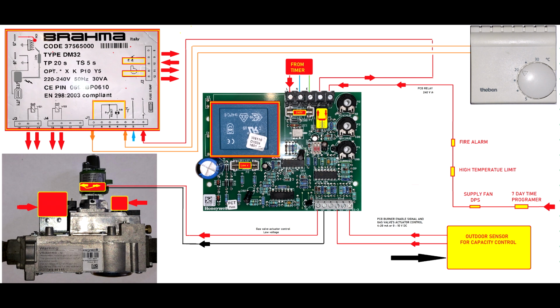And even if the Brahma controller is enabled and the control capacity is enabled, it doesn't mean the Brahma controller will initiate the heating, because you see you have a thermostat, and the thermostat is supposed to close the circuit between 3 and 7. And at the moment this system is on standby. Outside is very cold, the timer is asking for the boiler to go, but maybe inside your home it is warm enough. You have a nicely insulated home and you do not demand heating. That's the thermostat, which says, okay, look, you're on standby just in case the temperature drops.